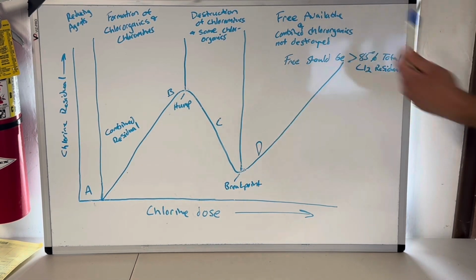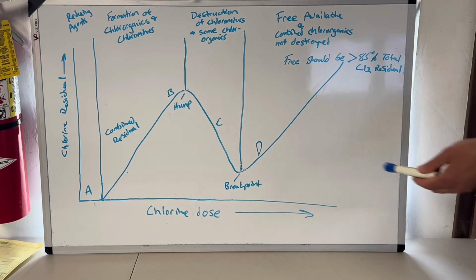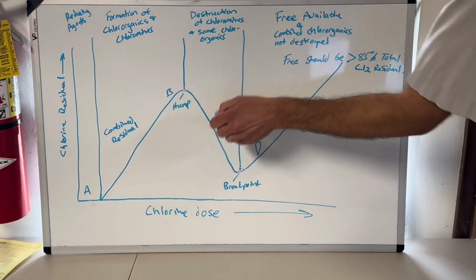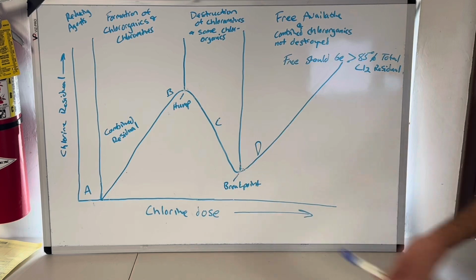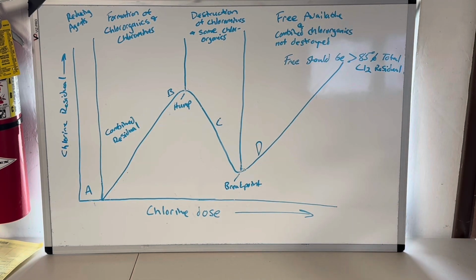That's when I truly started to understand this, by the way. I was finding that I was pumping more and more chlorine, and I wasn't getting it. I was hanging around a 0.5 in my contact chamber. That's not a place you want to be living at a wastewater plant. And I figured out, holy cow, I'm chasing my tail. I had no free ammonia in there. Let me back off a little bit.